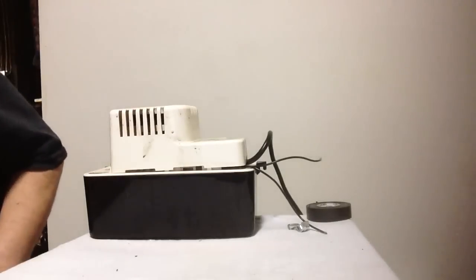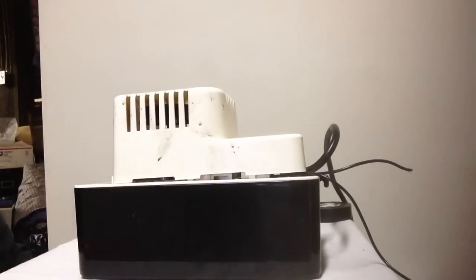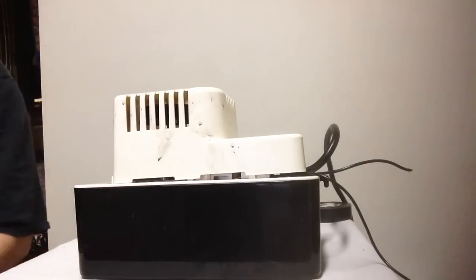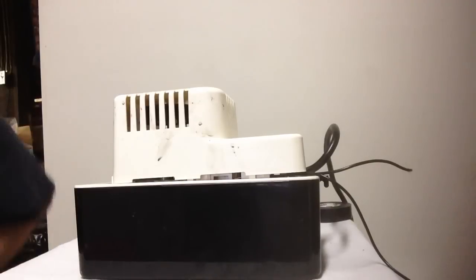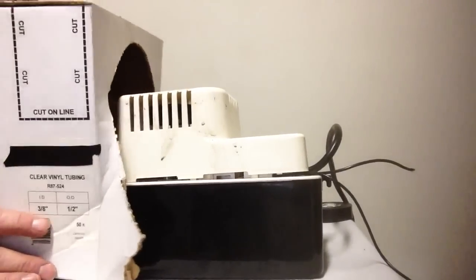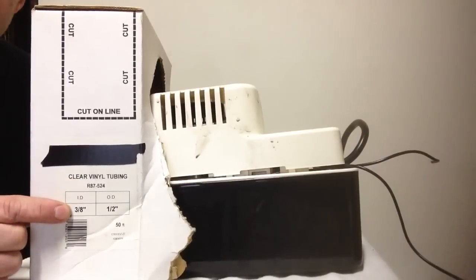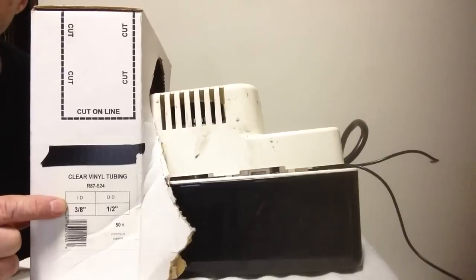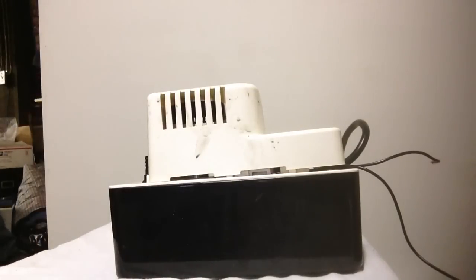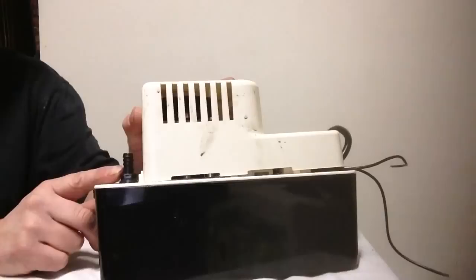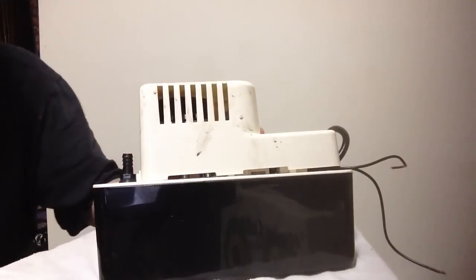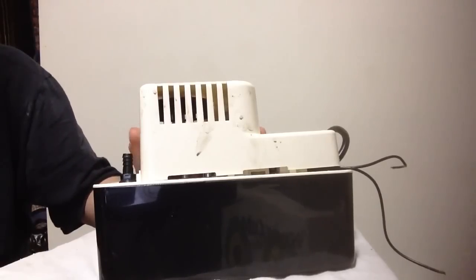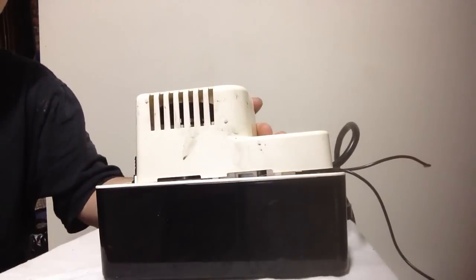Now when you order your condensate line, you want to order a three-eighths inside diameter, half-inch outside diameter tubing. The three-eighths inside diameter will fit over top of this because this is three-eighths and you want your pipe to be three-eighths on the inside. So that's very important when ordering your tubing.